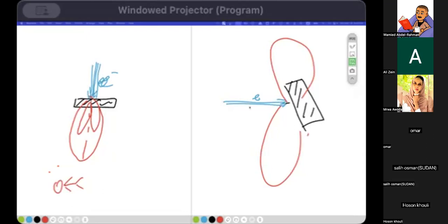Okay. So this is an electron and a target. How electrons are accelerated is a different story. We can accelerate them using an X-ray tube, or we could accelerate them using a LINAC. In X-ray tubes, the energies that we could reach are roughly around 300 keV. It's difficult to accelerate electrons to higher energies. In diagnostic radiology, this is fine because we want to use these low energy beams for imaging. That's okay, no problem. But in therapy, we want to reach megavoltage beams.